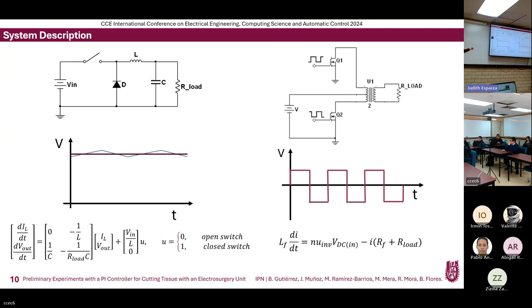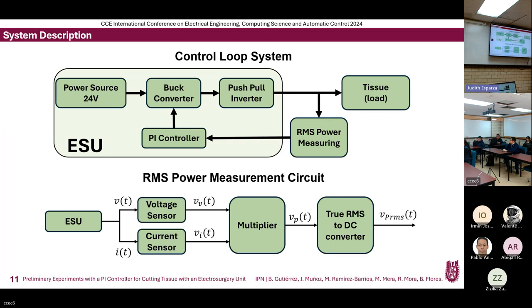Our control loop system consists of our ESU — a 24-volt power source, the buck converter, push-pull inverter, and the tissue as the load — along with a proposed RMS power measurement circuit, which provides the signal to the PI controller to regulate the RMS output power applied to the tissue. The RMS power measurement circuit consists of two sensors: a voltage sensor and a current sensor. These signals are multiplied to obtain a voltage proportional to instantaneous power, and then a true RMS-to-DC converter is used to obtain a voltage proportional to the RMS power.